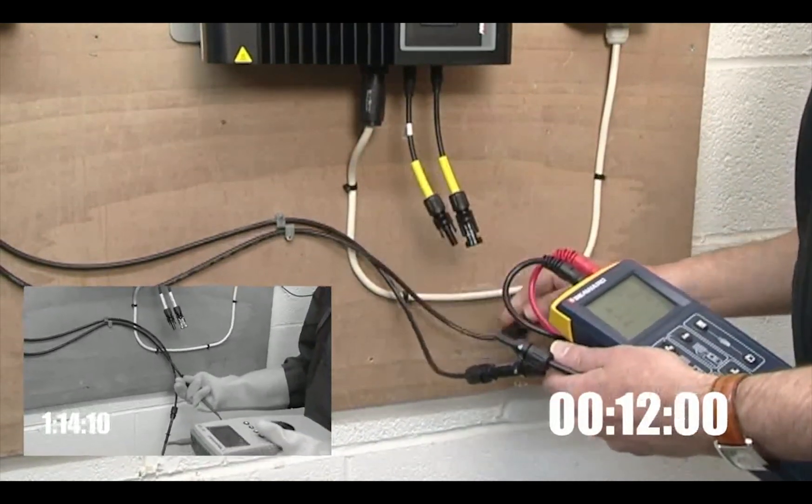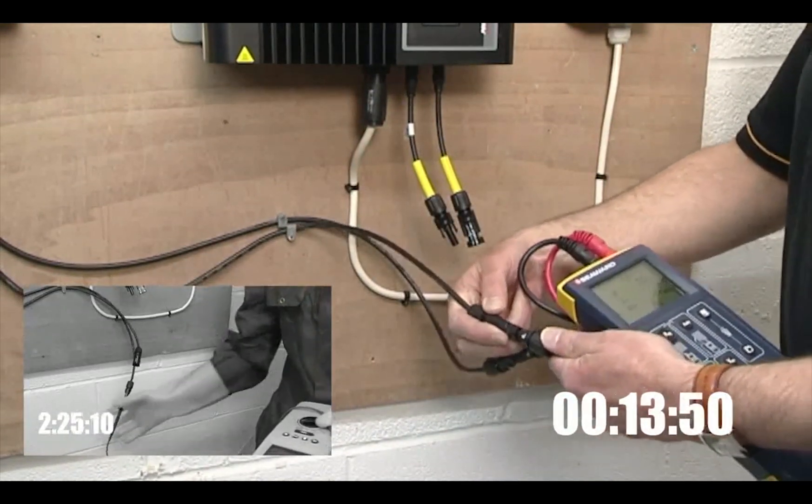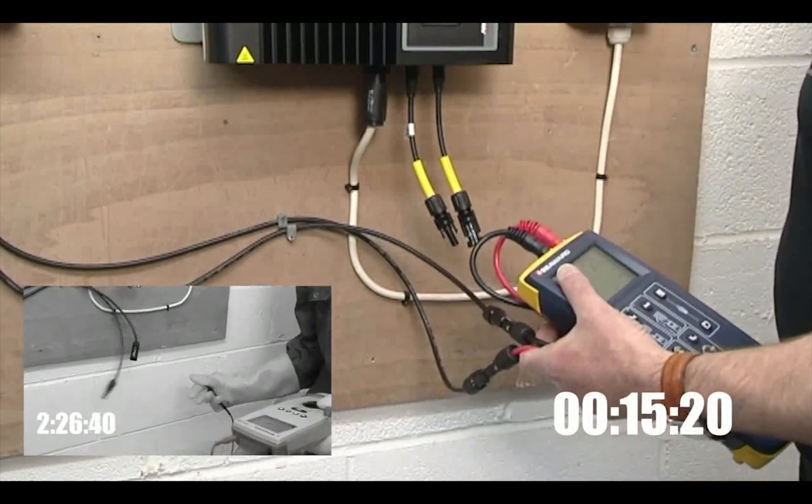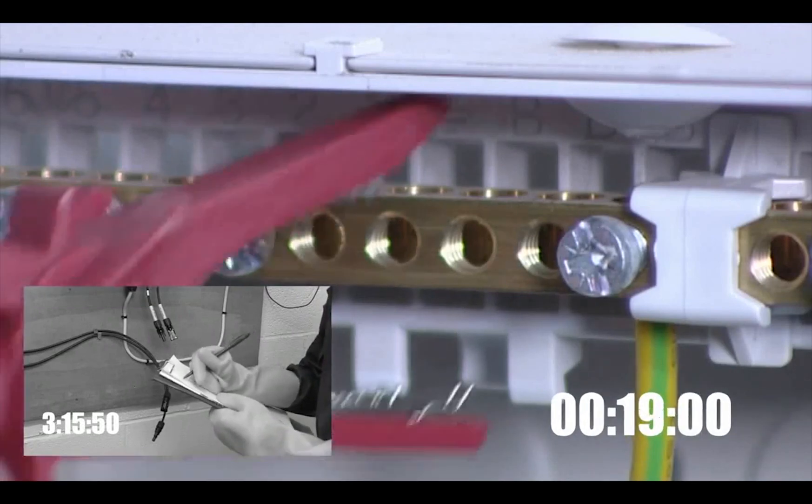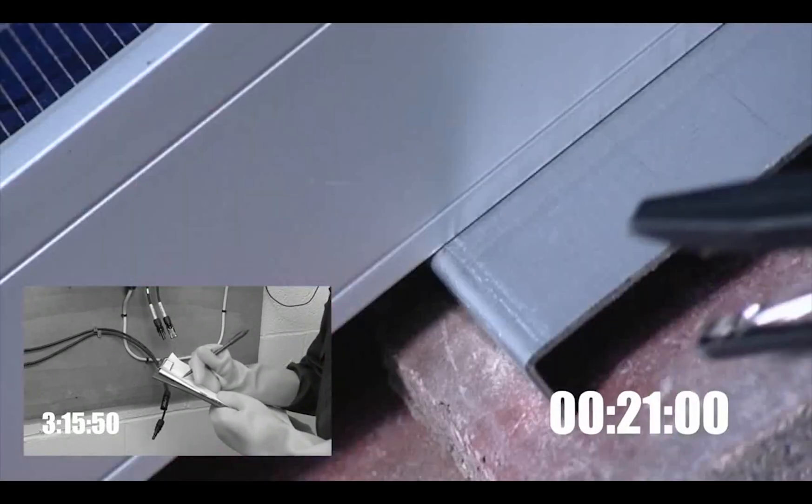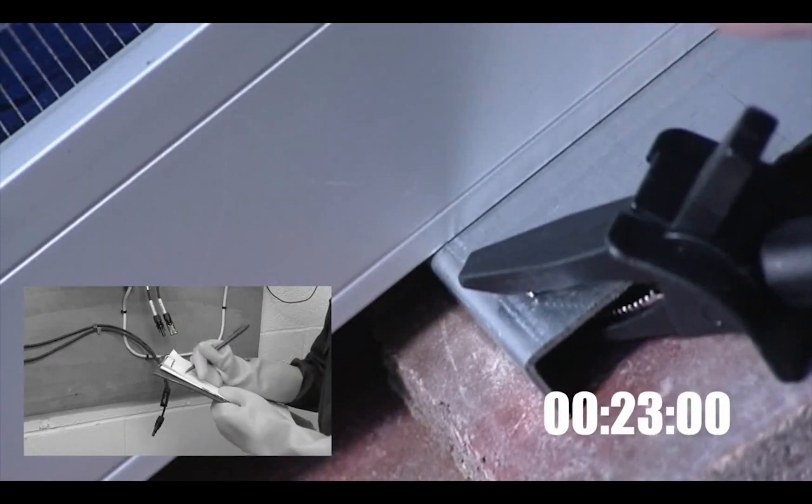In the small screen we're using an insulation tester for the open circuit voltage test. It's taken over three minutes to complete. Attach the crocodile clips to the earth and to the metalwork of the array and that's just over 20 seconds.